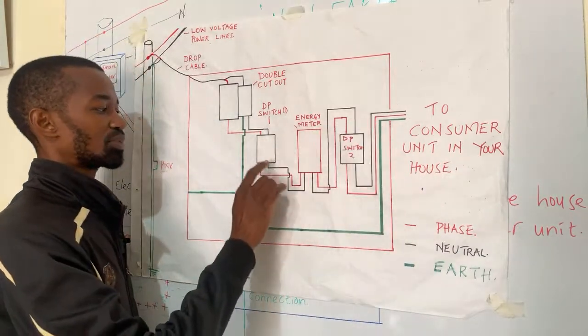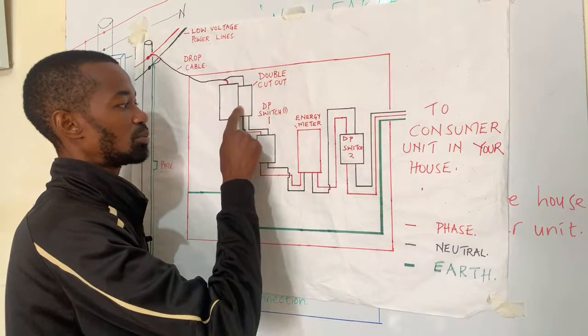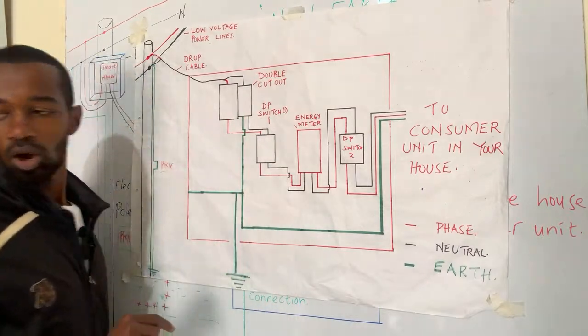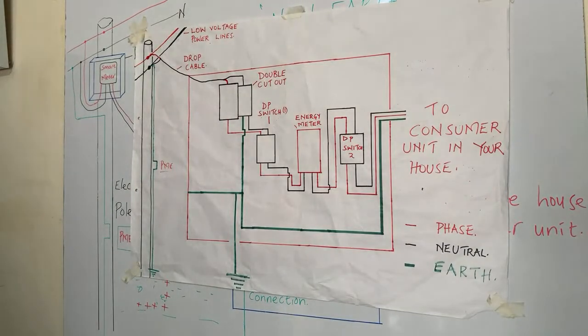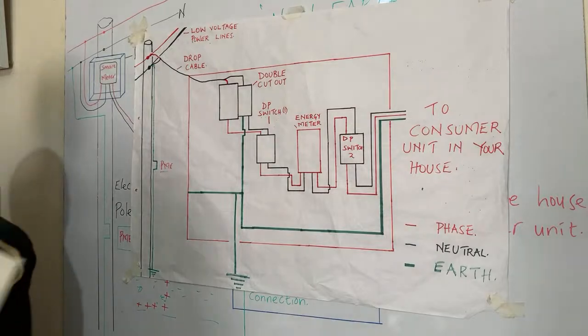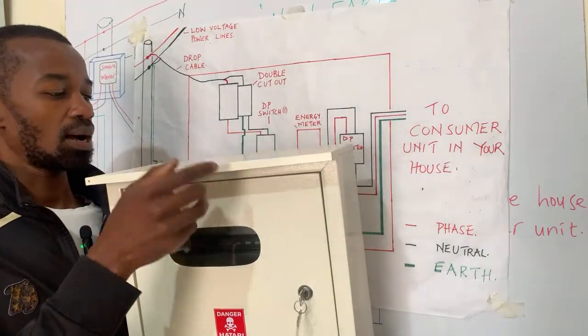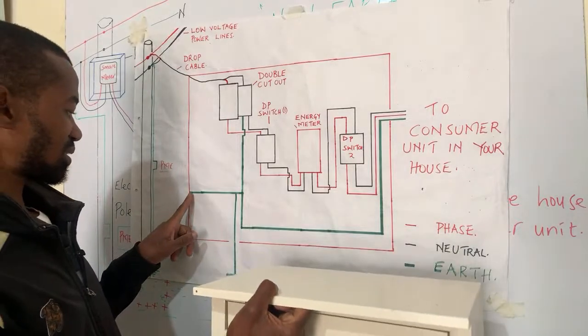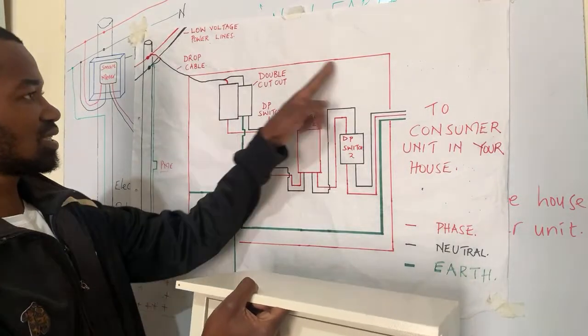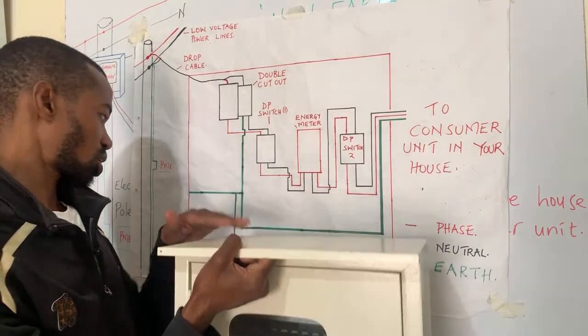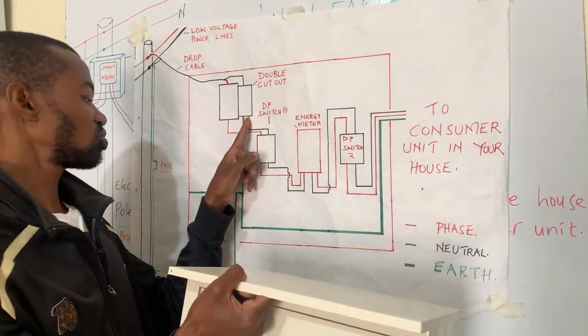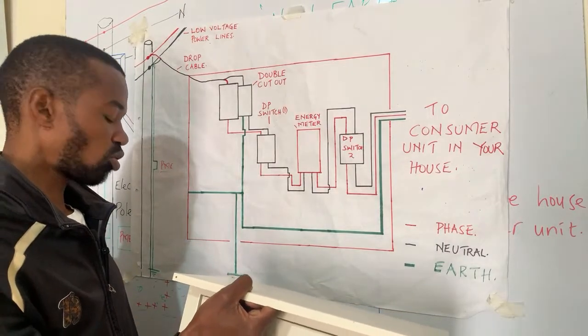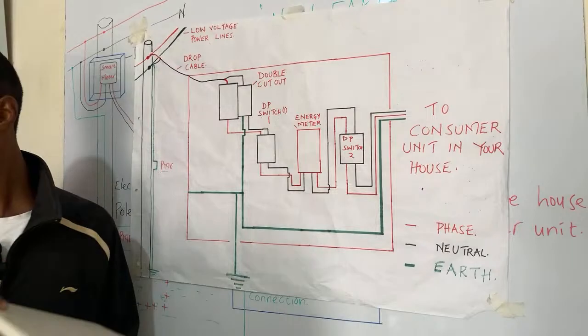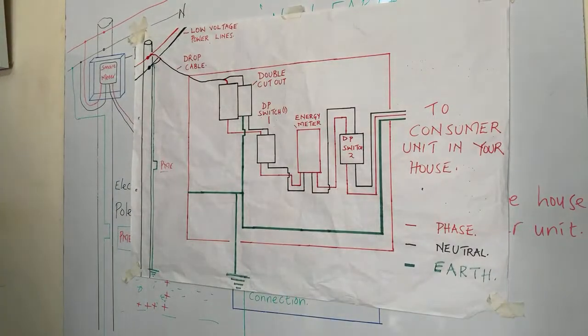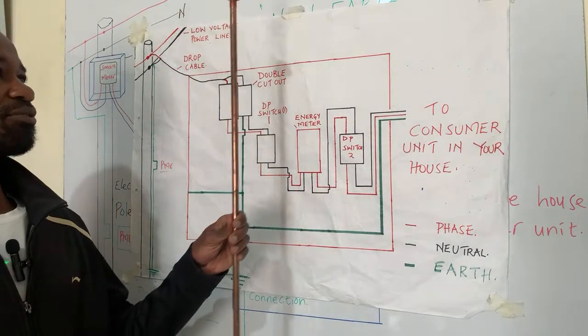At this time, our earth connection, which has been bonded already, will have to be connected again to the meter box. So you have another bond at the meter box whereby the earth, as you can see, I've drawn it from this particular point, this red representing the meter box. So the earth connection will be bonded with the neutral, and then from there it will go all the way to the ground, where it will get what we refer to as the earth rod, right? So here we have the earth rod.